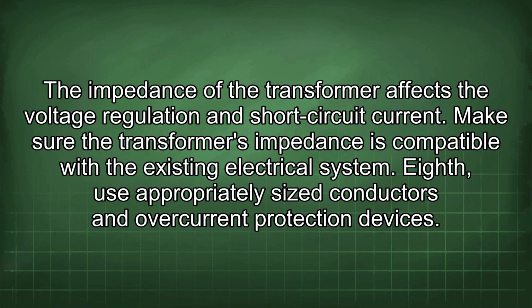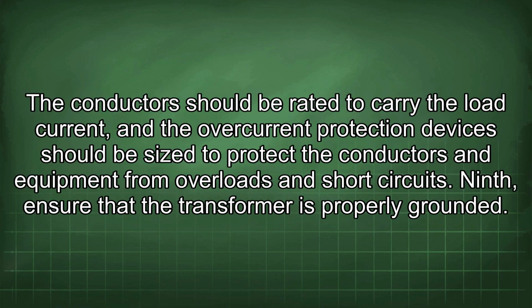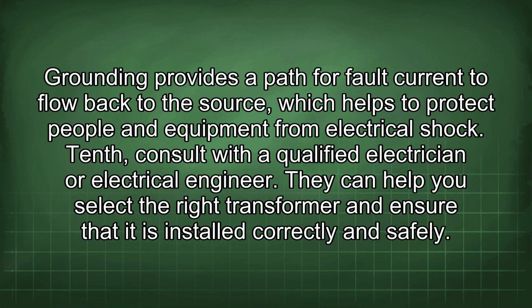Eighth, use appropriately sized conductors and overcurrent protection devices. The conductors should be rated to carry the load current, and the overcurrent protection devices should be sized to protect the conductors and equipment from overloads and short circuits. Ninth, ensure that the transformer is properly grounded. Grounding provides a path for fault current to flow back to the source, which helps to protect people and equipment from electrical shock.